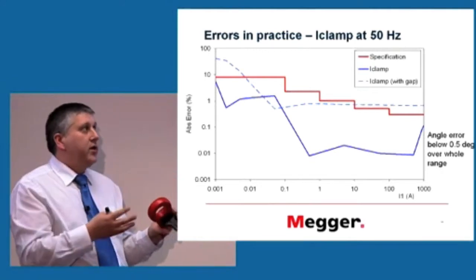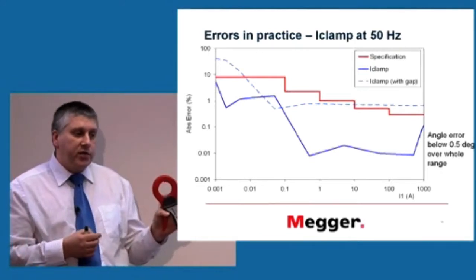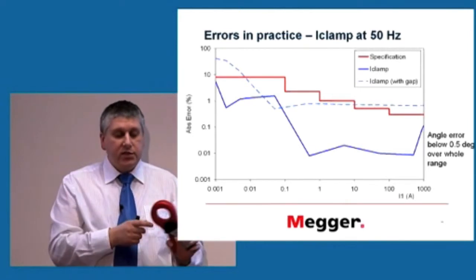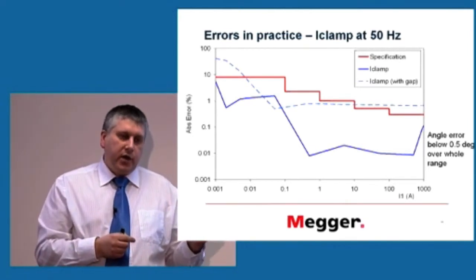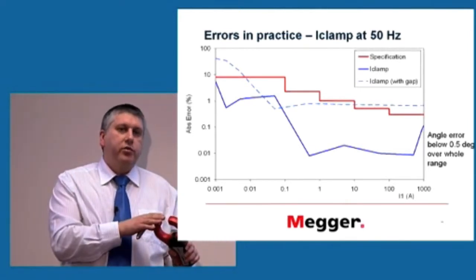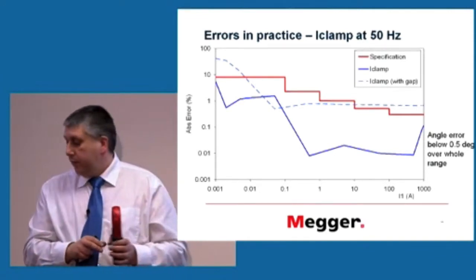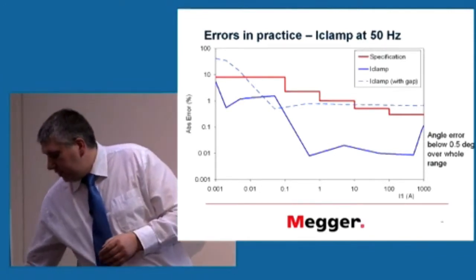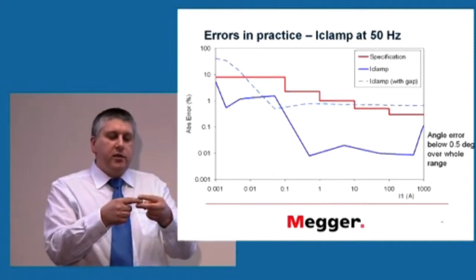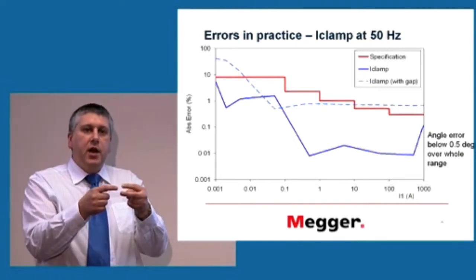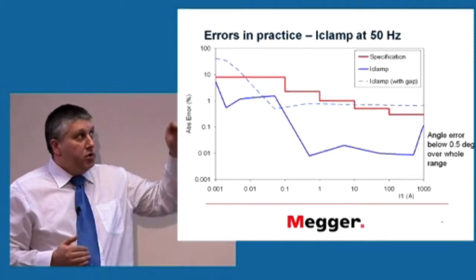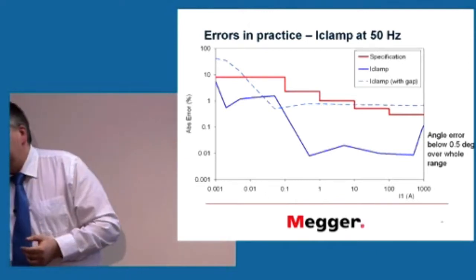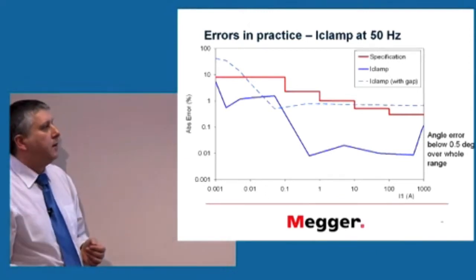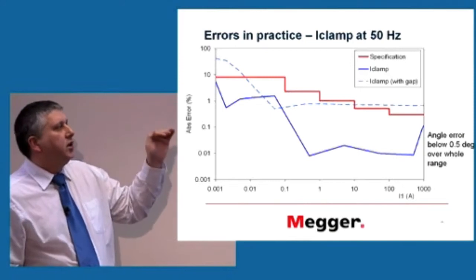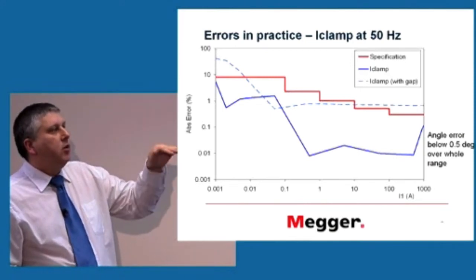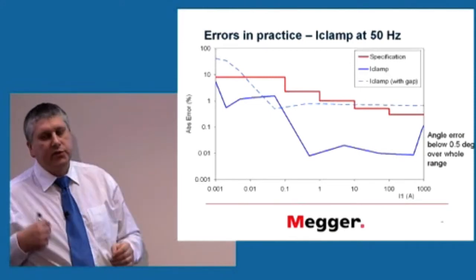There are ways of overcoming this, and you might see on some other versions, not on this one, because this is rated for higher voltages, hence no sharp corners can be involved. It has to be flat. But some other versions might have a number of teeth which will engage, and that will improve the immunity to any gaps which might be between the cores. And the angle error, I'm not showing it here just for clarity, but it's below half a degree for the full range as measured for this device.